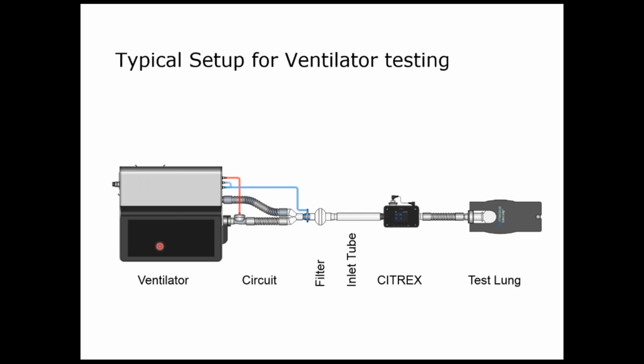We would have the ventilator or the anesthesia machine, then its normal circuits with sensors and whatever is necessary. Then we would have our CITREX here, and at the end we have the test lung. The CITREX part consists of a filter and an inlet tube and then the measuring device itself. The filter protects the CITREX from any dust or dirt, and it also helps in the laminarization and in the accurate measurement. The inlet tube is a laminarization tube which helps in a precise measurement of flow.